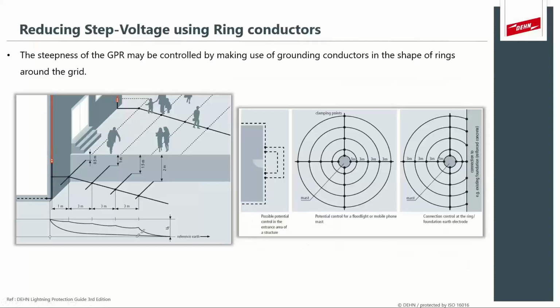The second thing we can do is adjust the shape of the grid. This is an example on the right of potential control in the ground at walkways or around structures, for example a floodlight or a mobile telecoms mast or something like that. If you look on the left, we see that at different depths we keep installing conductors further and further away. By doing this, we control the steepness of the ground potential rise to ensure that we don't have significant differences between points if someone had to walk there. So we can apply this method as well.